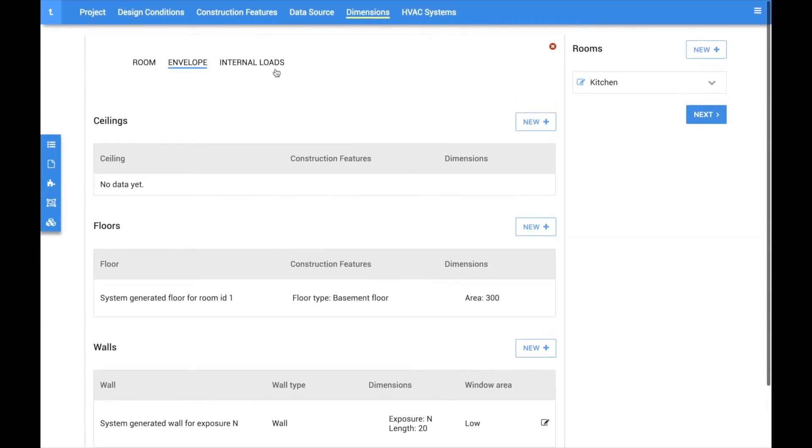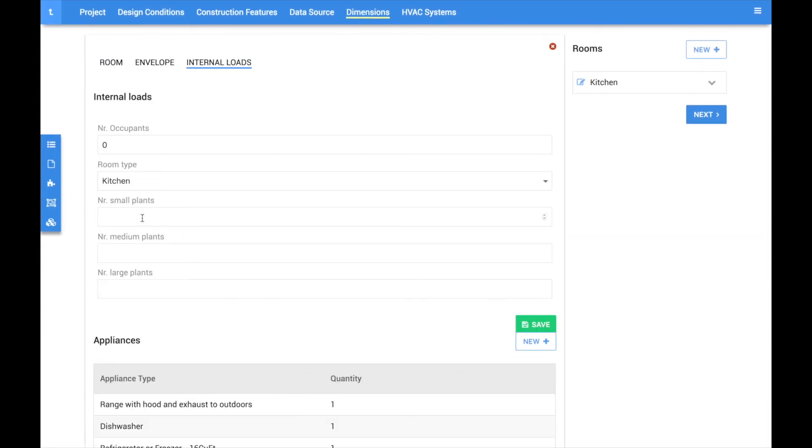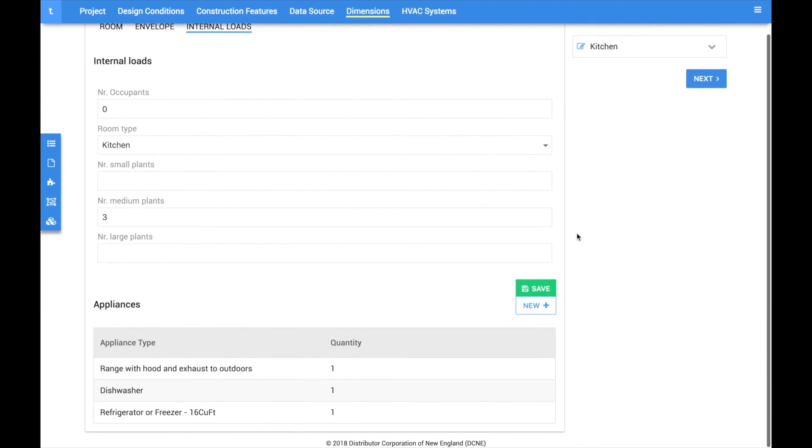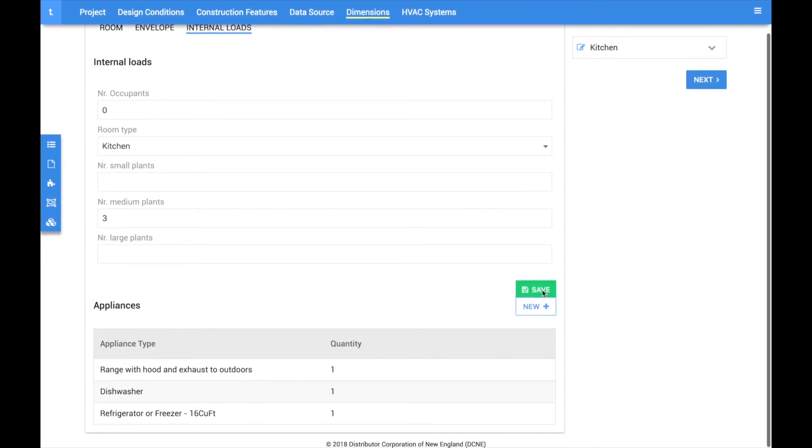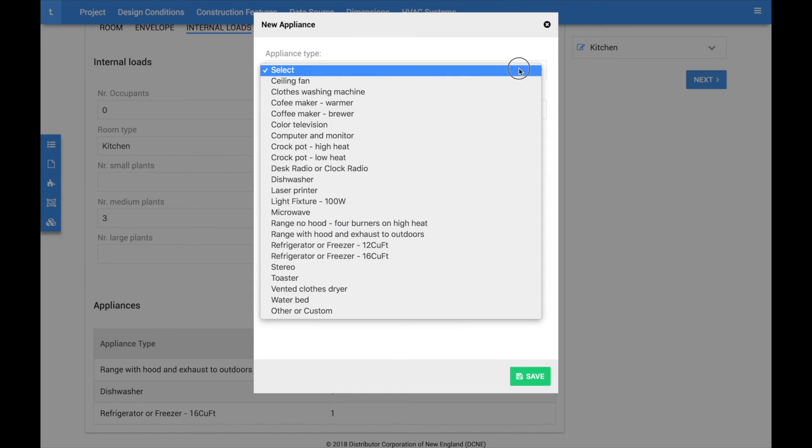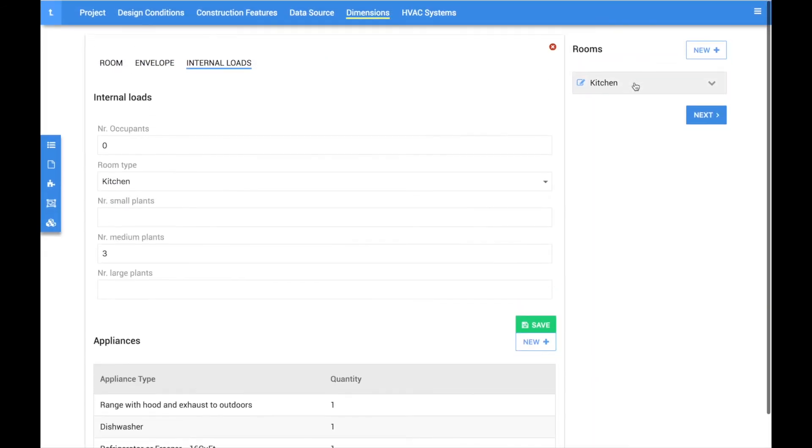Once you are finished editing the envelope of the room, you can click on the internal loads tab and manually assign occupants, plants, and appliances to the space. If you chose one of the predefined room types on the room setup screen, the appliances would have been automatically added to the space. Be sure to only add appliances that would normally be operating on a hot summer evening. Adding every appliance and light contained in the room will lead to an inflated cooling load.